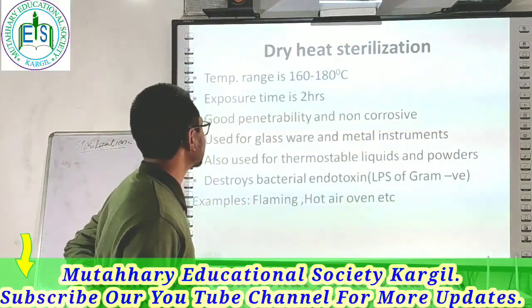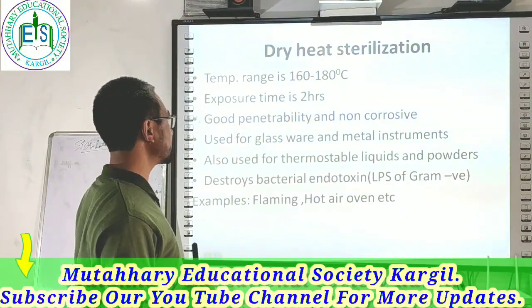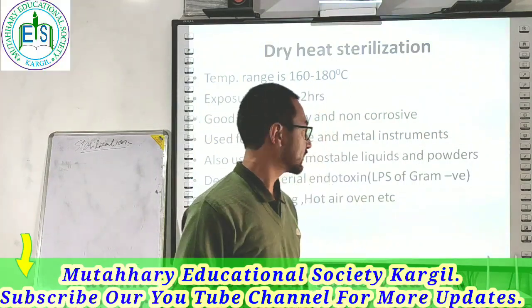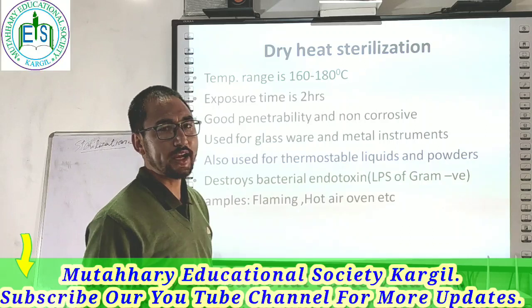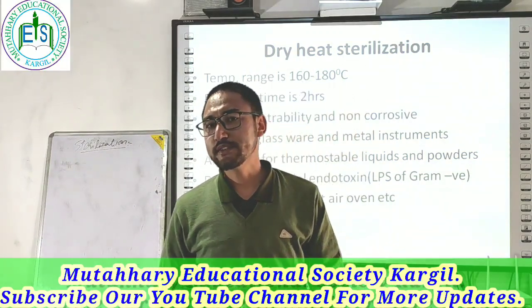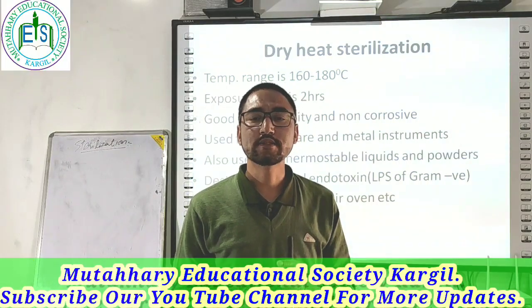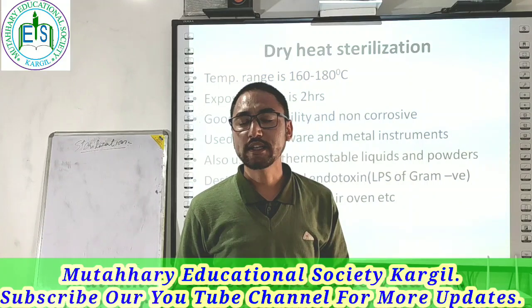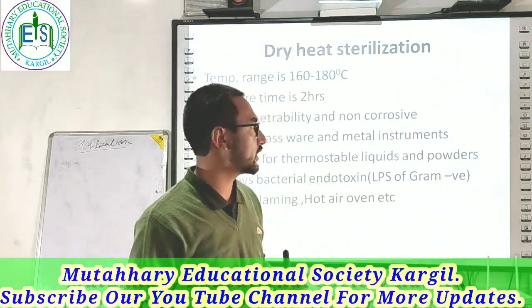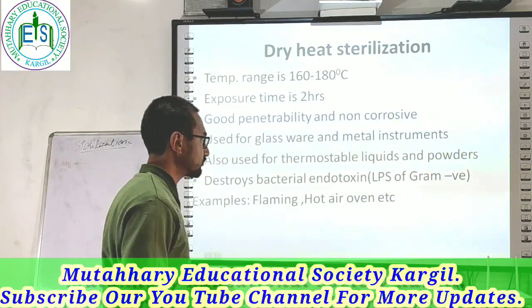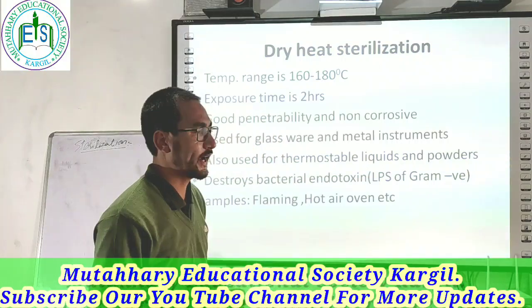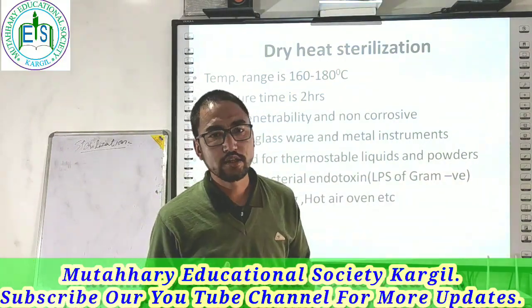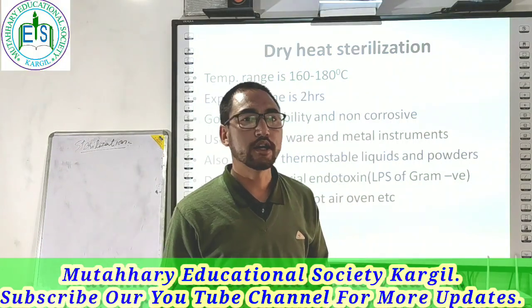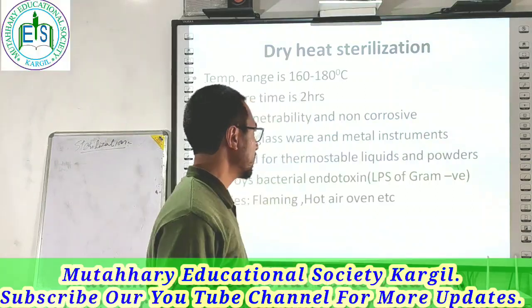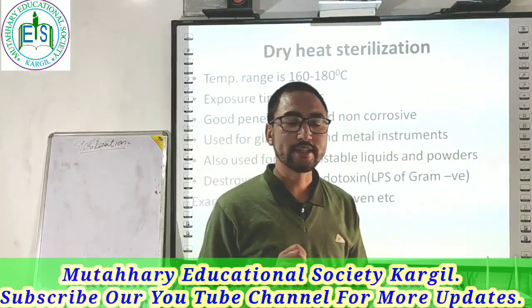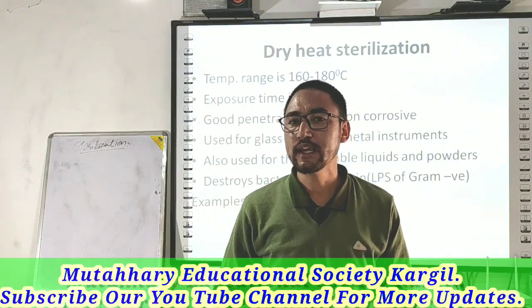Dry heat sterilization, temperature is again 160 to 180 degrees Celsius. The exposure time required is around 2 hours. It has good penetrability and non-corrosiveness. Non-corrosiveness means that the characteristic features of those substances will not be changed. For example, if you use a metal, the metal would not rust when you do heat sterilization by the dry method. It is also used for thermostable liquids and even powders, say certain chemicals or media, water. If you have to use them, you can use the dry method of sterilization in order to remove the microbes. It also destroys various kinds of bacterial materials like endotoxins.